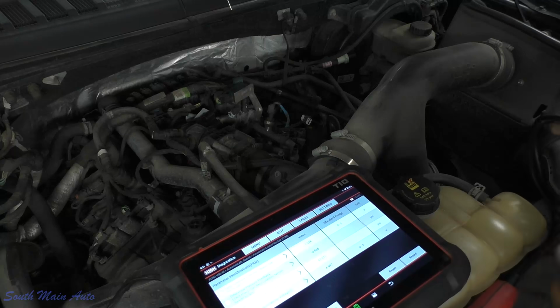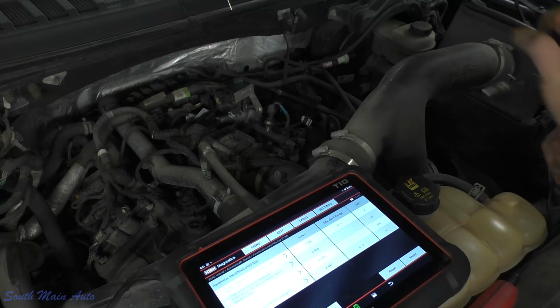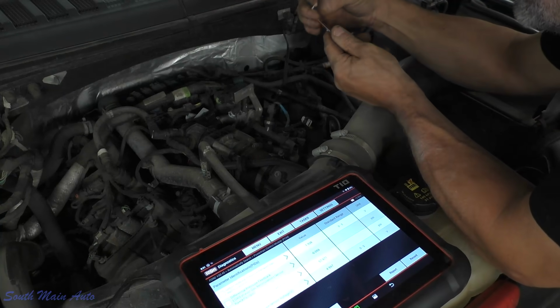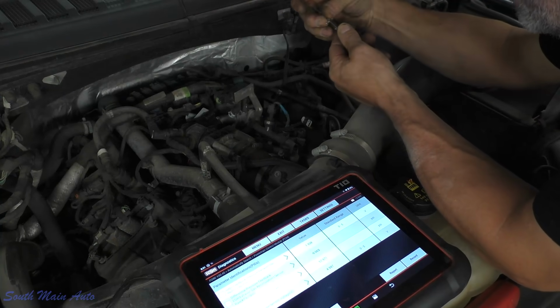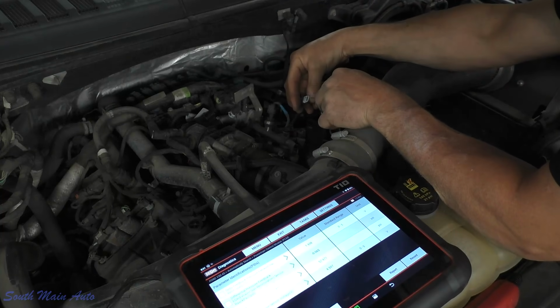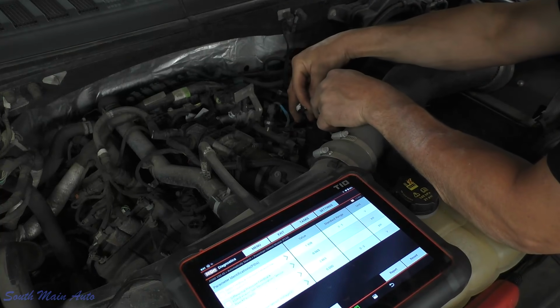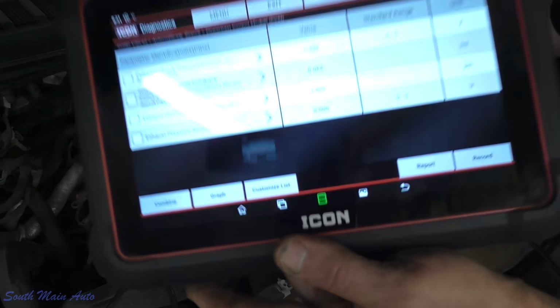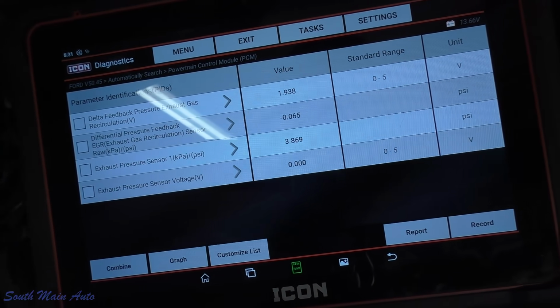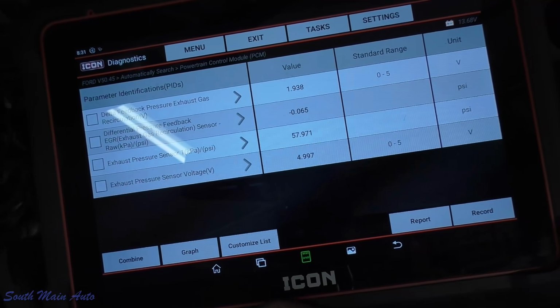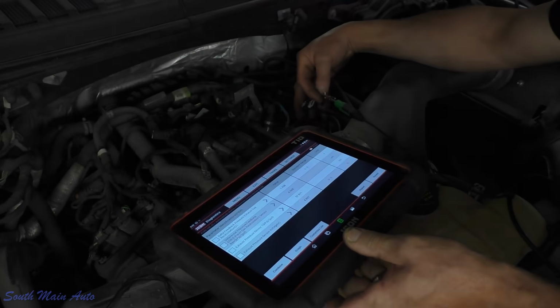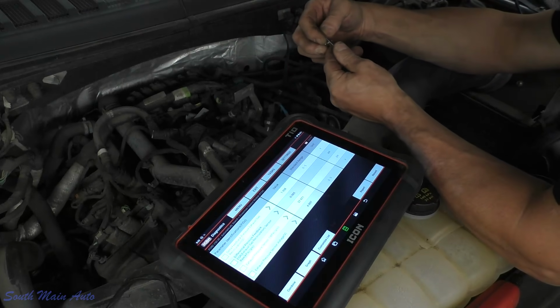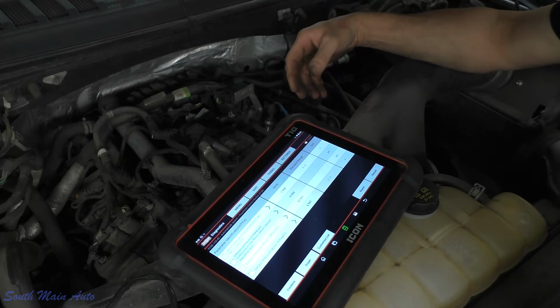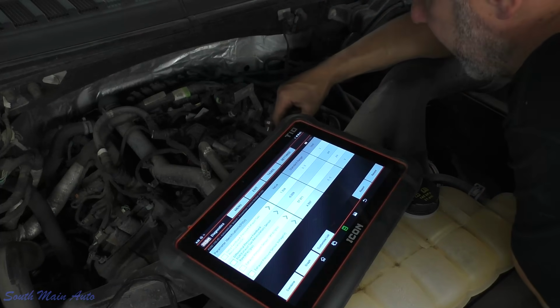Okay, so we know we have everything there to make it work. If you want to prove to yourself, just take your ground - usually I would do this with a test light - and we're going to ground our signal wire very lightly, and we should see that pull that bottom number to 0. Take the ground away, back to 4.99. So that's a quick circuit integrity check, and that's that in a dime sack, they say.